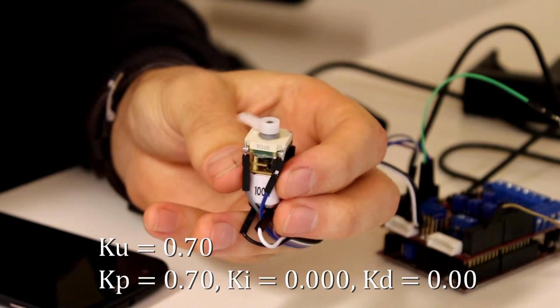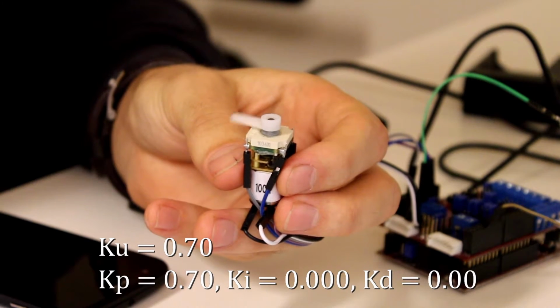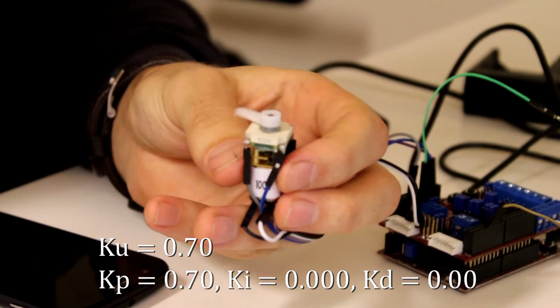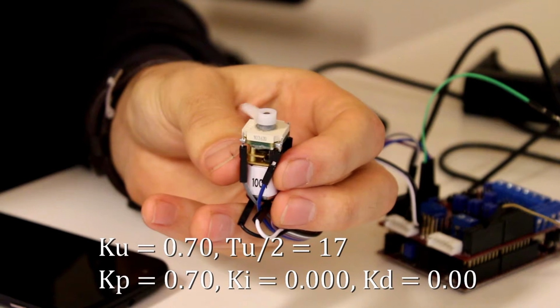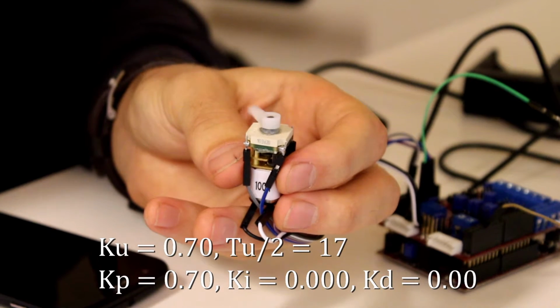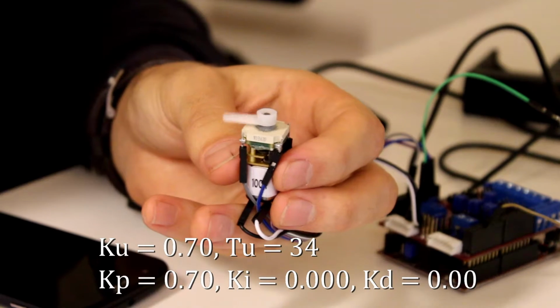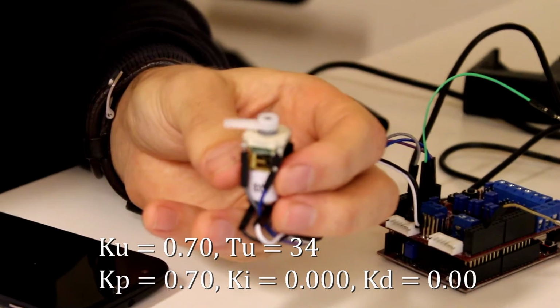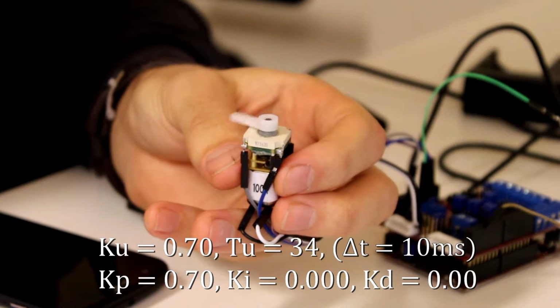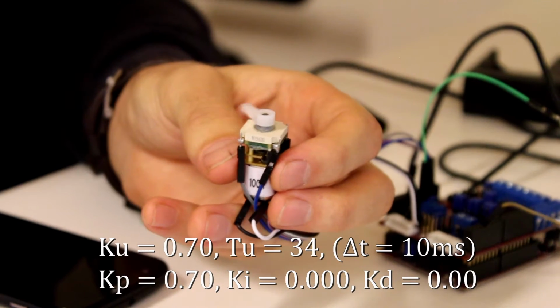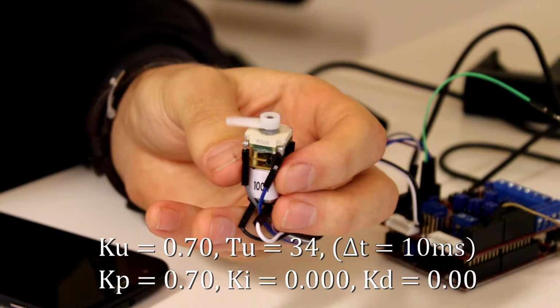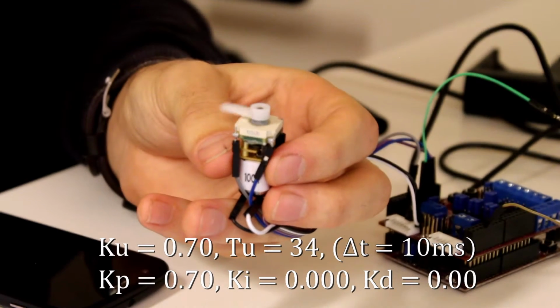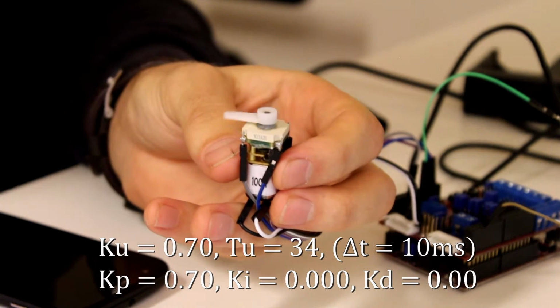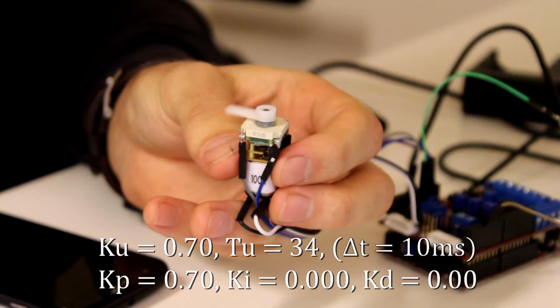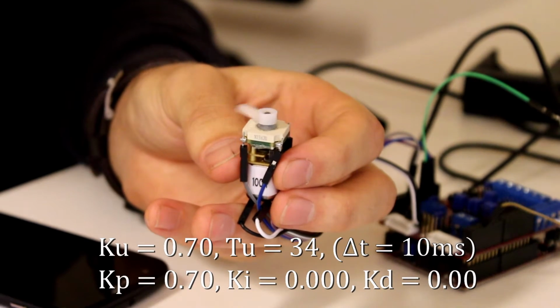So from the screen I can read off values for the period, for one of the swings, around 17. So we double that, that will be 34 for a period. Again, we're not multiplying by the dt, because we also don't have that in our PID formula. So we will set our p-value to 0.6 times Ku, according to the Wikipedia formula that we're using, which is 0.6 times 0.7, is 0.42.